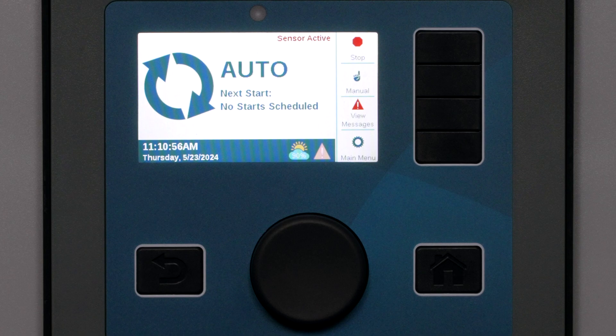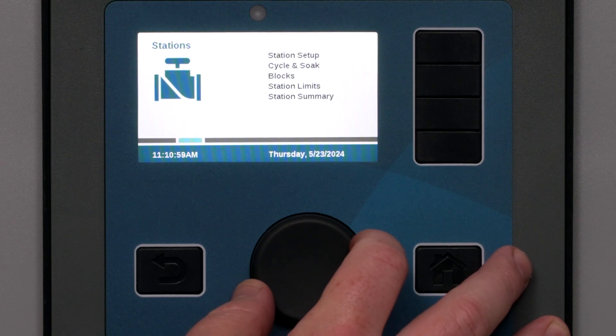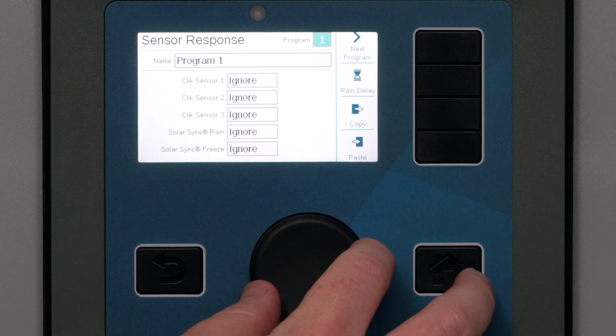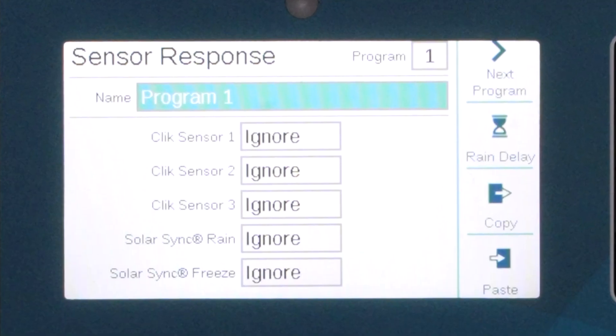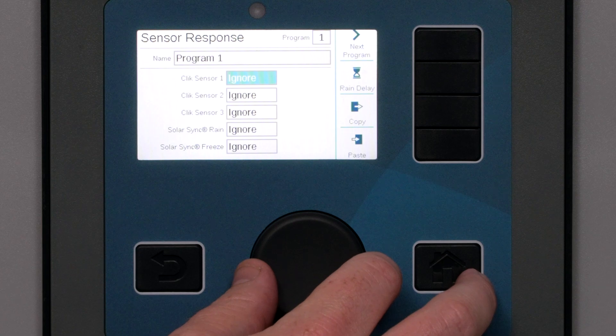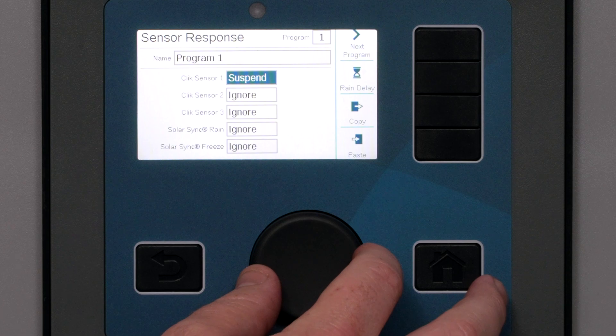The final step for both Solar Sync and Clik sensors is to configure the desired sensor responses. The ACC2 controller shuts down irrigation by program — we must tell each program what sensors will affect it and how. At Program 1, we can see all three Clik sensors, plus the Solar Sync Rain and Freeze inputs if we have a Solar Sync enabled. Each sensor has three possible settings. Ignore means the selected program will not be affected by this sensor.